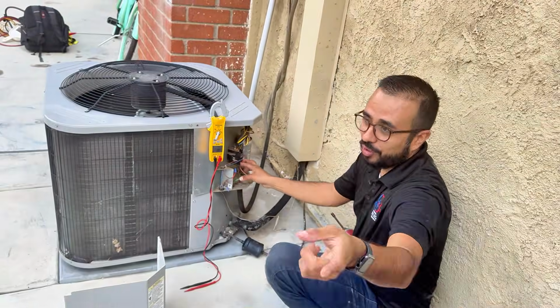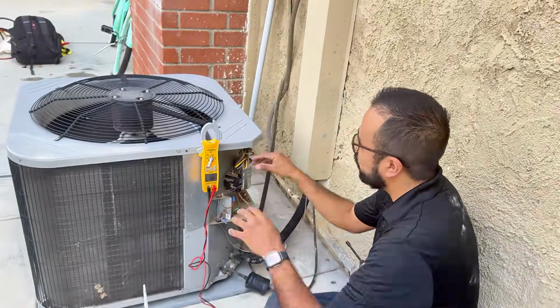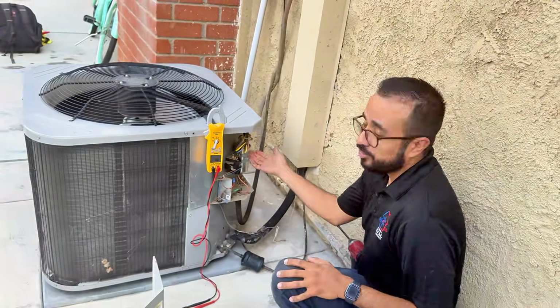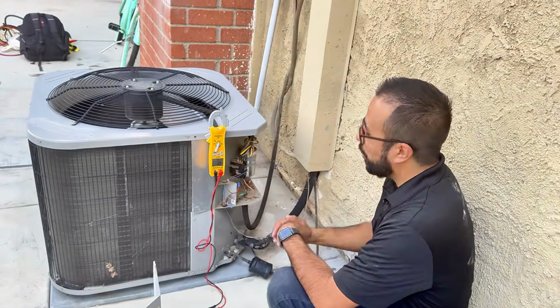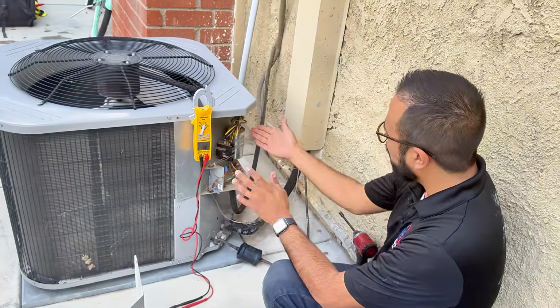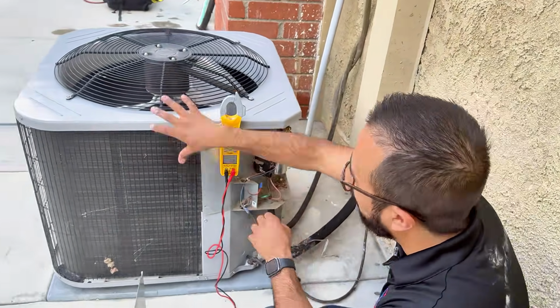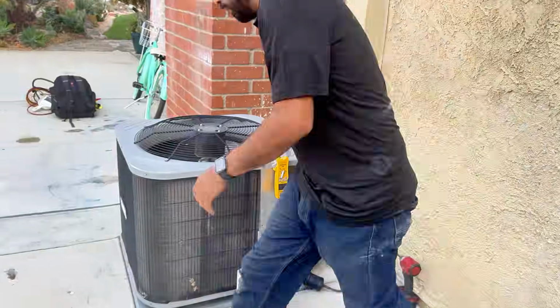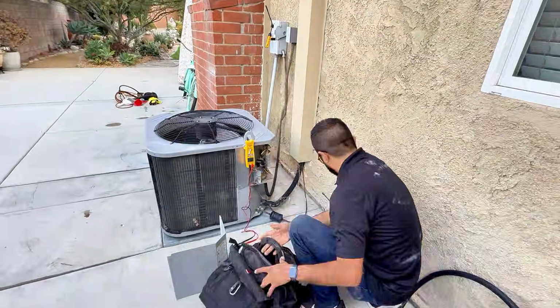So never trust a disconnect, never trust a breaker. You are always supposed to confirm with your meter. Check line one and two, make sure you have 0 volts, then check line one to ground and line two to ground. And if you get 0 volts, then yes, now you can work on the system safely.